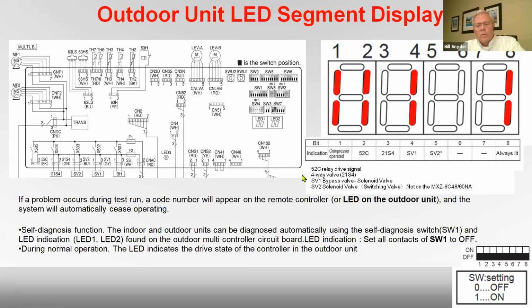And you open up the cover, and I've had this happen several times where somebody will open up the cover and say, hey, I've got a fault code on the outdoor unit. It's 1111. That is not a fault code. This particular display, we use it in like 3 different manners. In this case, these are called flags or segments. Mitsubishi calls these flags. And there's a 1, 2, this is a flag 3, this is a flag 4, 5, 6, 7, and 8. So there's 8 different flags across here.